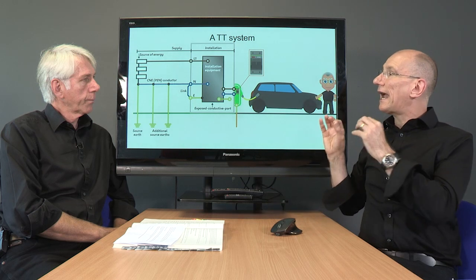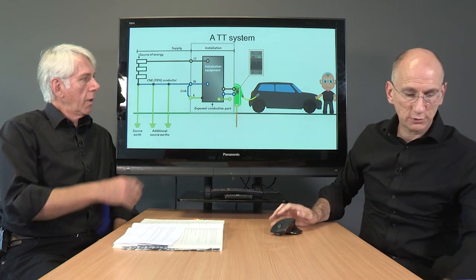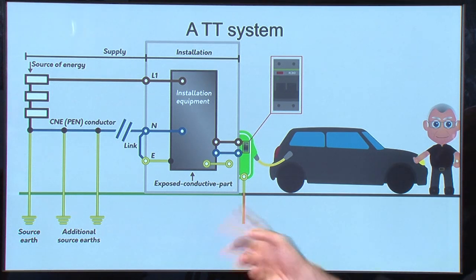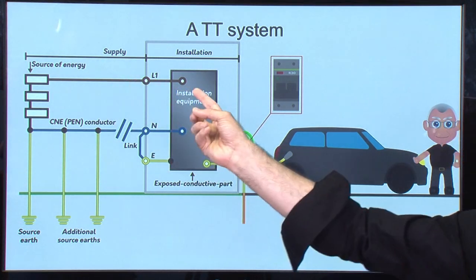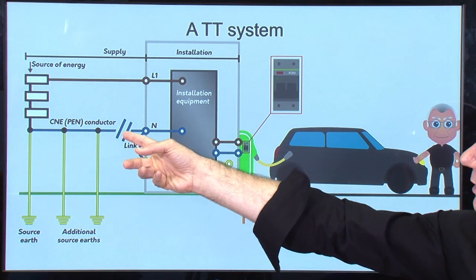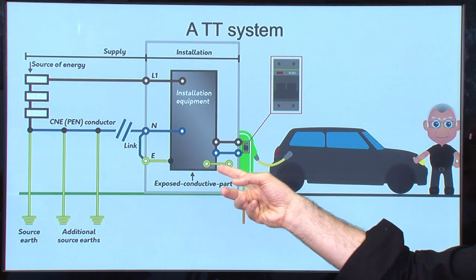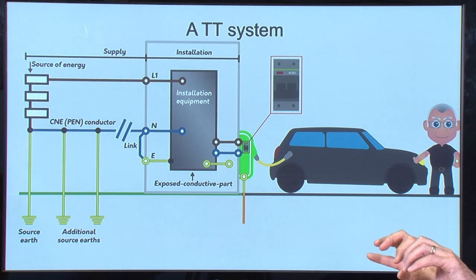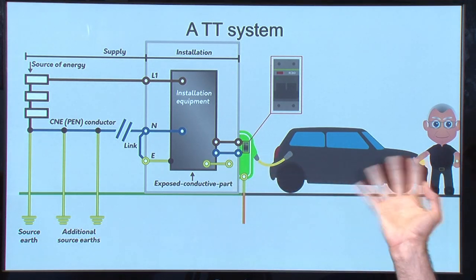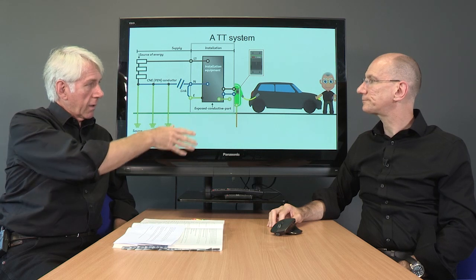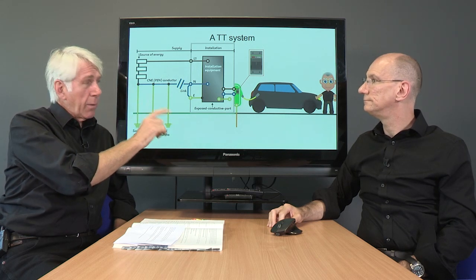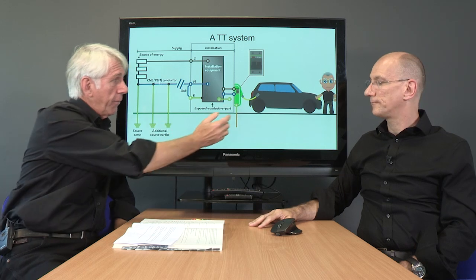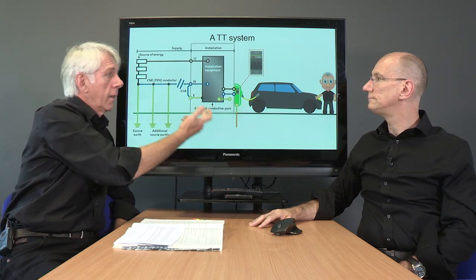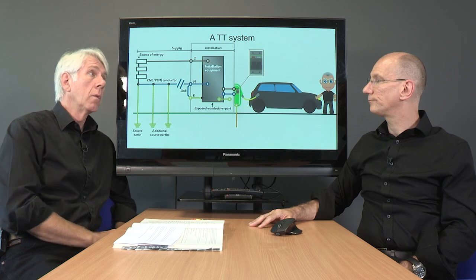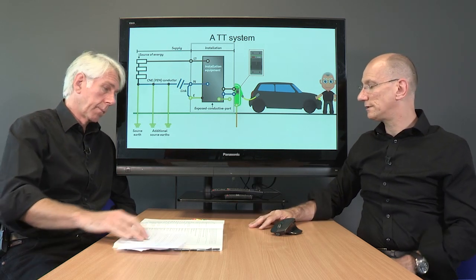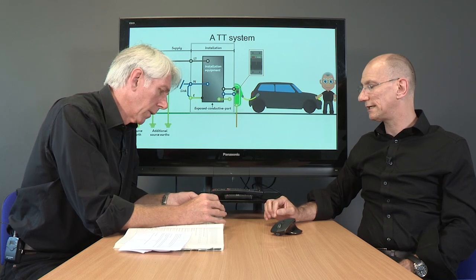So this is an option, which, as I will show you, is helpful when you lose the neutral, because current comes in and goes back, there's a broken circuit there, it passes through to here, we'll carry along to the cable. Because it's separate through an insulating gland or something, this would not be presented at this point here. But regardless of the business of driving in a spike and whatever, we still have the proximity challenge. Yes? If the distance between this installation and this installation is too small, there is a requirement in 7671 that deals with this, which is basically simultaneously accessible.